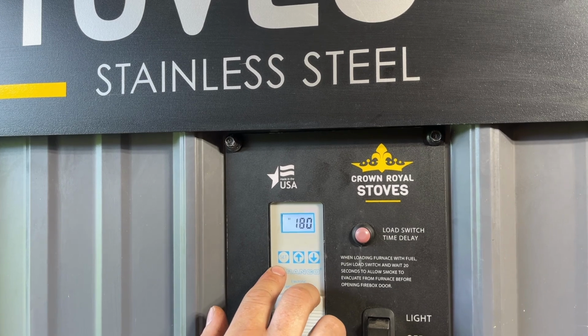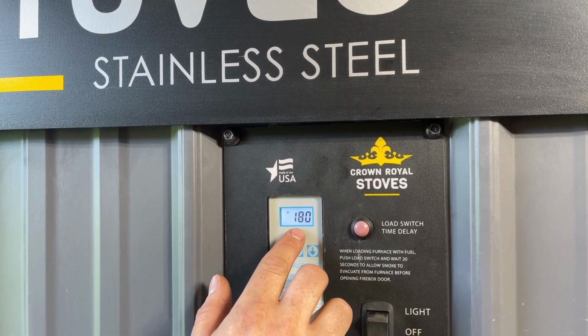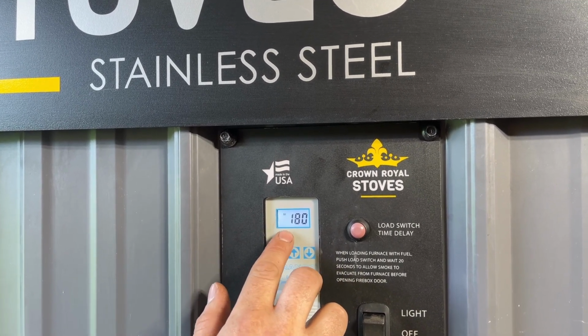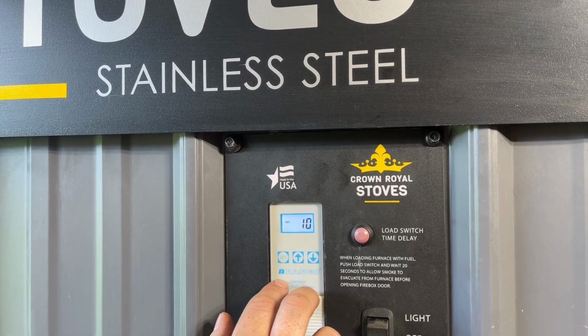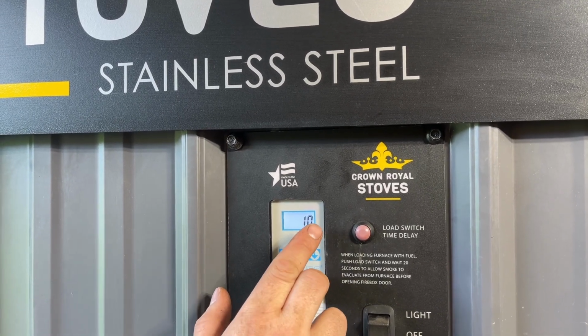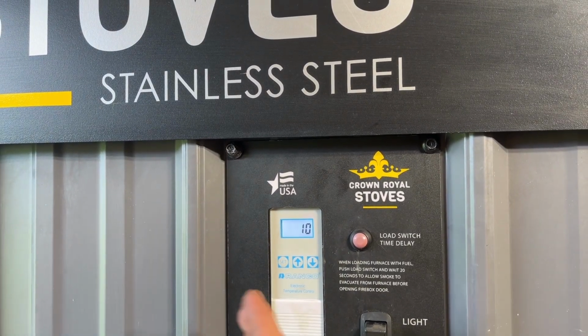The next step is the set temp of the boiler, and I've got that set for 180 degrees. This is your differential, so I've got it set for 10, which means the boiler is going to kick on at 170 degrees.